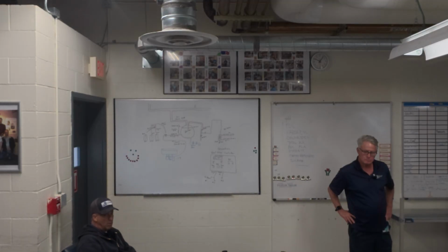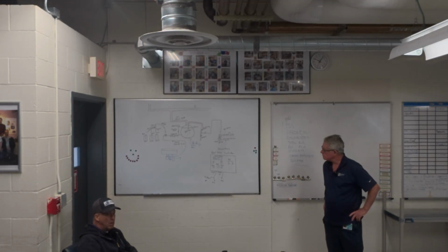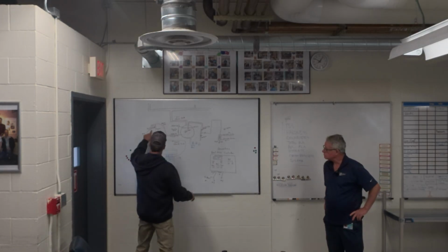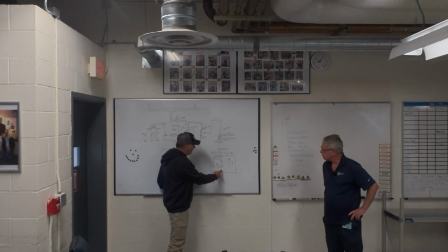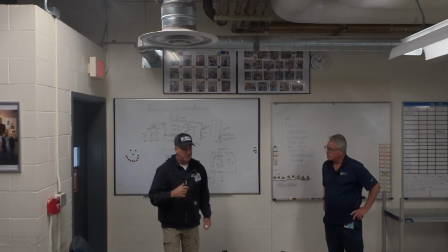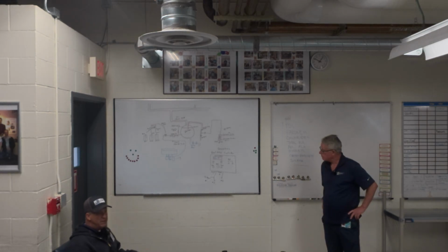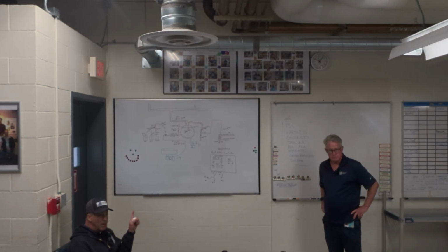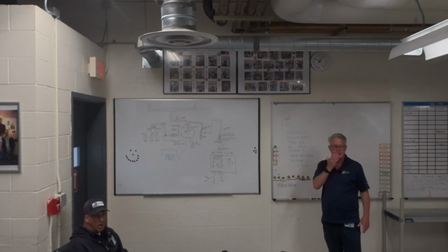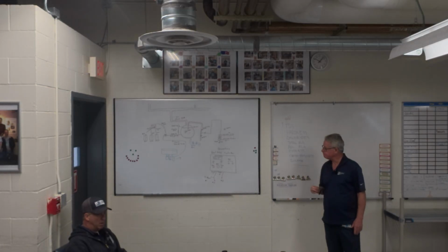One more thing, what did you mention was on the BAS? I believe these controllers are capable of producing an output that goes right into your field panel to the BAS. The Symmetrics units don't do that though. We're working with the flow meters and controllers on the new boilers to get a totalization out to the BAS. That's how it's being done. But the Symmetrics have no output, they don't do anything but take pulses and run the pump relay for a designated amount of time. It's just a relay system, that's it.